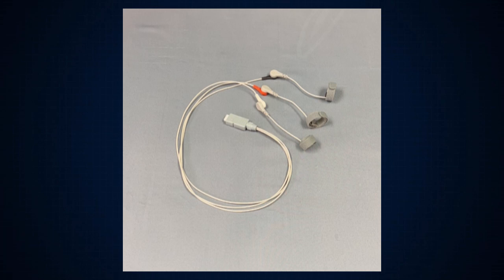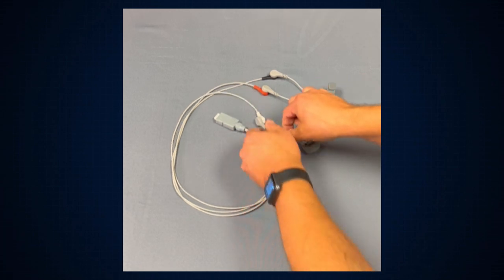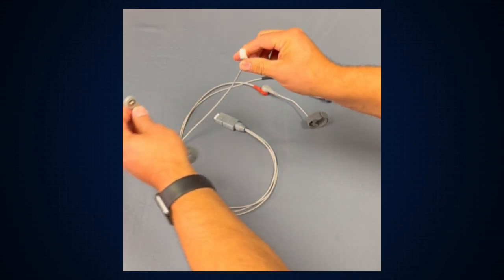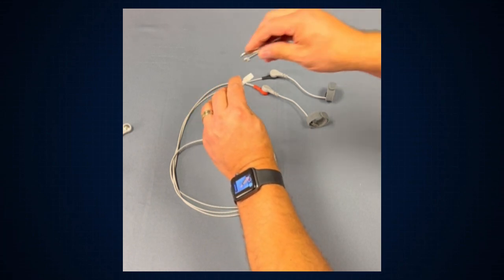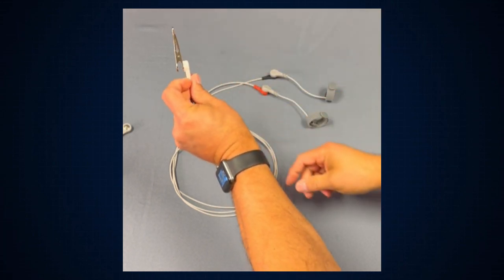This is our 3-lead ECG lead wire set with limb plates. To apply, just simply attach the limb plates, one to the right front. Actually, more specifically, the white will be to the right front, red will be to the left rear, and black will be to the right rear. That will give you a true lead-two diagnostic quality ECG tracing. The 3-lead wire set is typically utilized when you're doing a workup or a screening. It is also important to note that we do have the option with our snap leads to disconnect the limb plates and go with a paddle clip or flat clip, if you will, for customers who prefer that over the limb plate design.